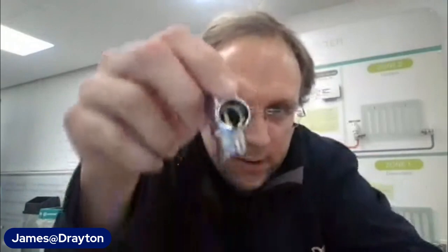Now, one of the things that makes balancing either a chore or much easier is something called valve authority, and that essentially means the amount of resistance that's built into a valve from the get-go. So before you even start modifying the shape or the size of the aperture, some valve bodies will inherently have a greater valve authority. And what I mean by that is, if you look at this lock shield here, you can see this is a standard lock shield, and the ports on this are wide open.